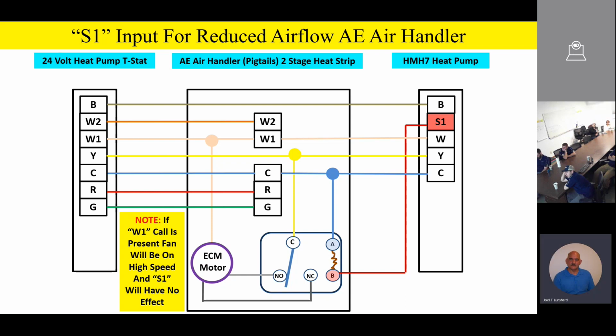I'd also like you to notice that if you happen to have S1 energized at that point, and I go to auxiliary heat, that fan, even though it has two speed commands on it, the ECM motors are designed so that if it has more than one speed command, it always takes the highest of the commands that it's receiving. So during an auxiliary heat call or a defrost call, we're going to drive that fan to a higher speed. In addition, W1 will be present one more time during an auxiliary heat call or during a defrost cycle. So that's basically how we wire this up.